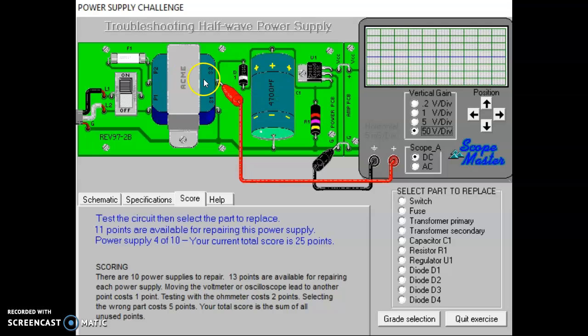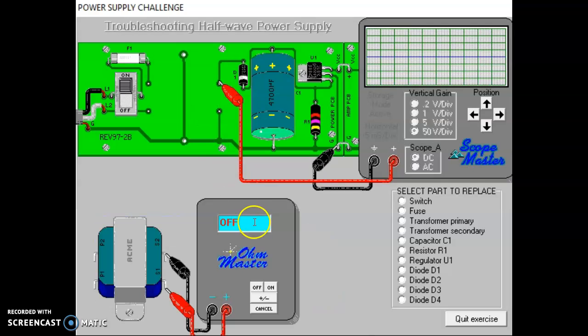To double check, if you want to check the secondary side, we can double click on it and pull an ohm meter out here. When I turn that ohm meter on, I see that the secondary coil has a flaw, an infinite resistance, meaning there's some kind of open in that secondary coil. The secondary coil of my transformer is my problem.